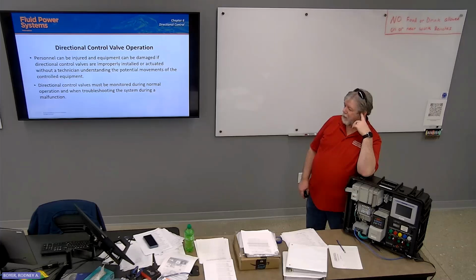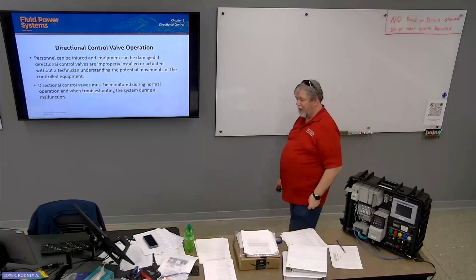Personnel can be injured and equipment can be damaged if directional control valves are improperly installed or actuated without a technician understanding the potential movements of the controlled equipment. Well, you always want to have a schematic. You can figure out if I operate this valve, what's going to happen. And not to call you out, Ben, but in his situation, like at work the other day where he couldn't find a schematic, could he have gone to the manufacturer's website, and do they typically have them on there? 99% of the time, yeah.